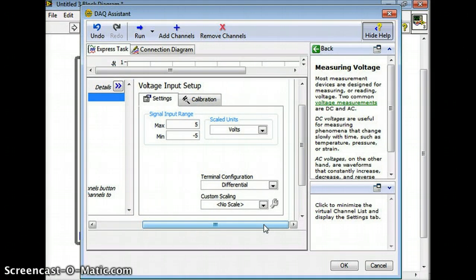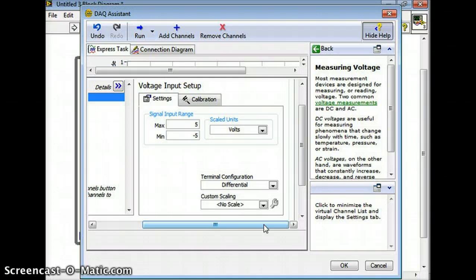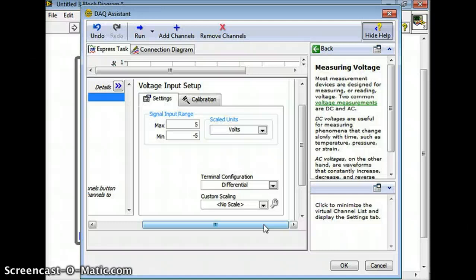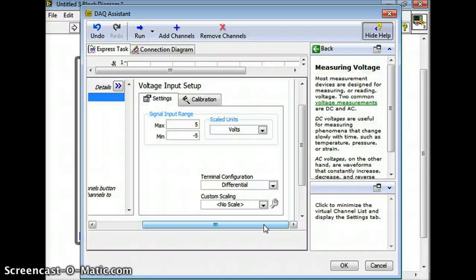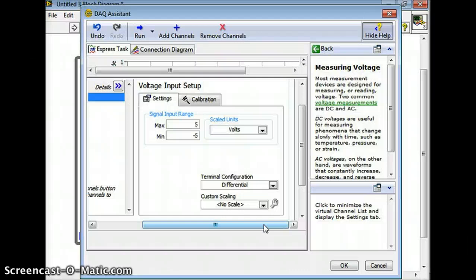So you've got your max voltage and your min voltage. Now when you pick your maximum and your minimum voltage it's really important to think about your type of measurements. Because if you're measuring a very small voltage you're going to want a higher resolution. The way that National Instruments picks the resolution of your DAQ card is it takes your dynamic range here of your voltage. So if you pick from minus 10 to plus 10 that's going to be a very coarse resolution - you're not going to have a lot of fine tuning with that.